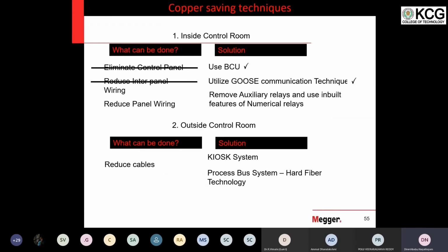What is GOOSE? Generic Object-Oriented Substation Event. This is actually defined in IEC 61850. The meaning is, in the examples we discussed, the status of the isolator and earth switch. Now, this isolator, breaker, all these things are called objects. That's why the second O, object. Object means isolator and breaker. This is as per the IEC definition. So this is generic information. The status of the isolator and breaker is generic information pertaining to a specific substation. So that's why it's called Generic Object-Oriented Substation Event.